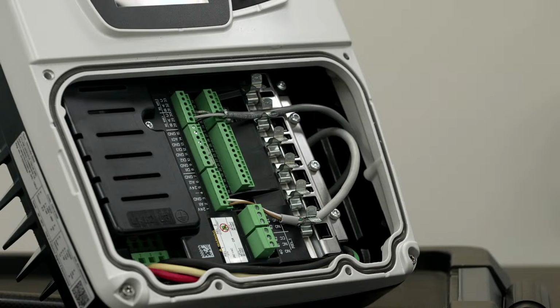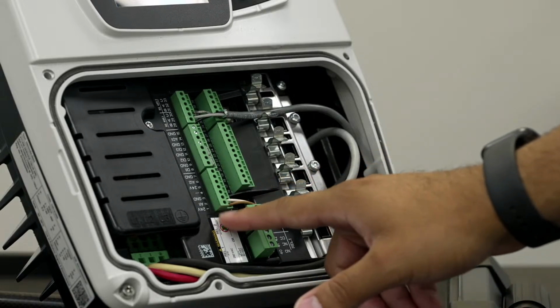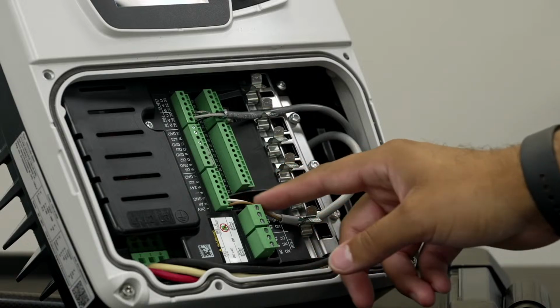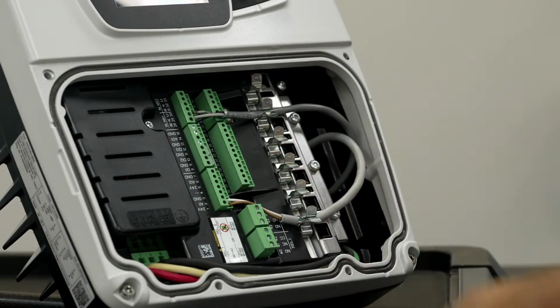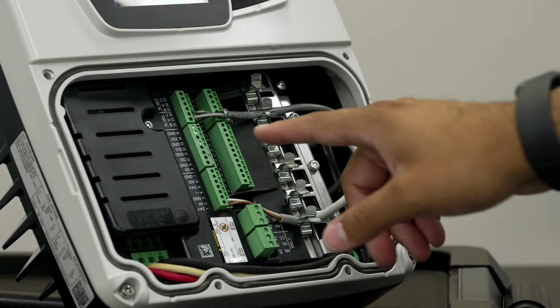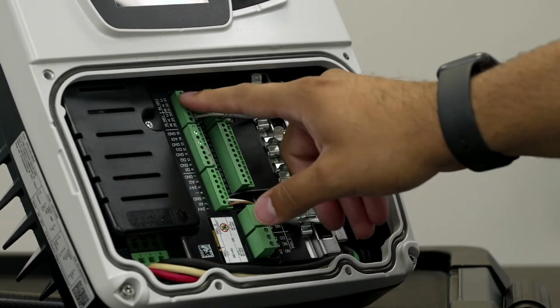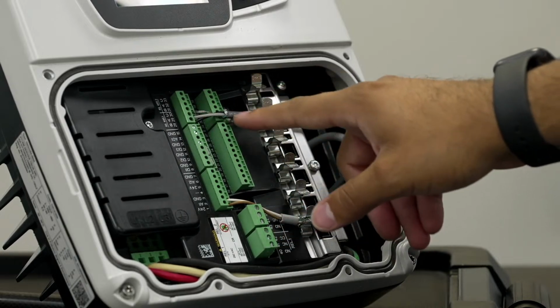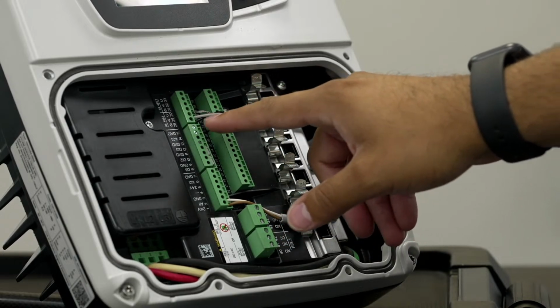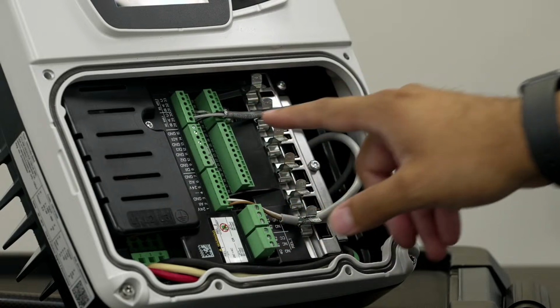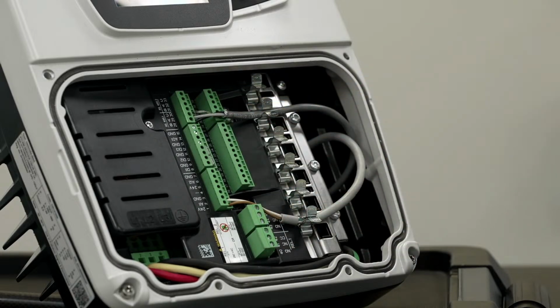Each unit is going to come standard with a 0 to 300 PSI transducer, 4 to 20 milliamp, and it will be analog input 1. So this cable you're seeing here is the transducer cable. And if you were going to run a multi-pump application, we have a bunch of RS-485 communication ports available. So this would be for multi-pump. We have it showing here, for example, it's going out to the next pump.